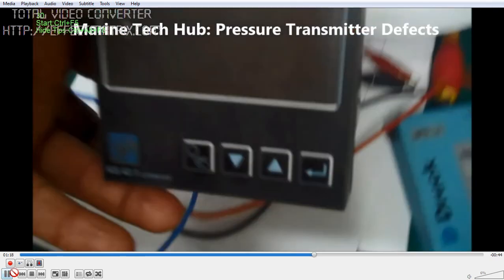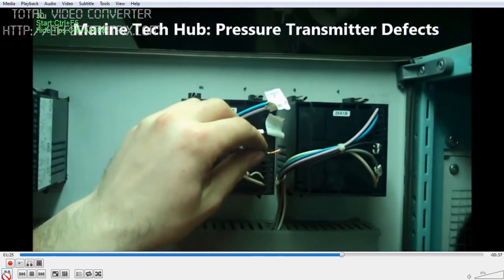This is the box that we have removed from its place. We will be checking whether this is working or not. What happened in our case was it was showing FAIL. We found out that when the pressure transmitter signal was given, it was not showing on the controller because the control voltage was not coming into the controller. You should know how to read the drawing. After checking, we are putting the controller back.